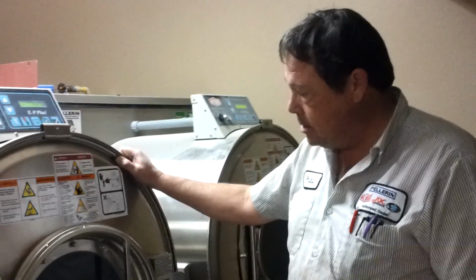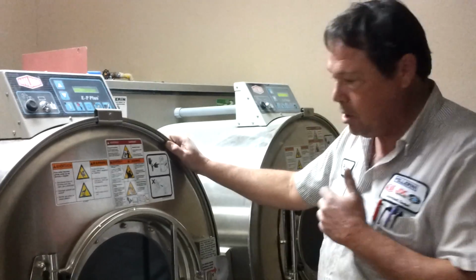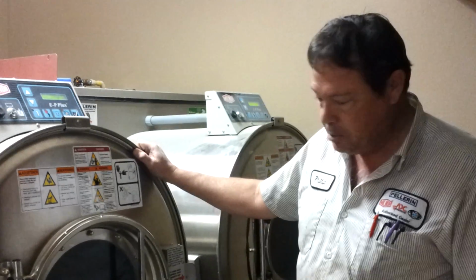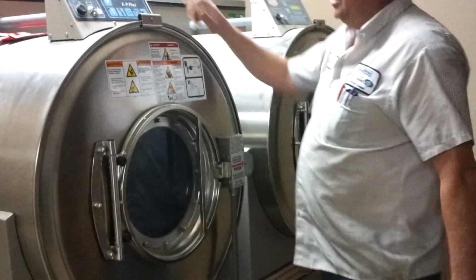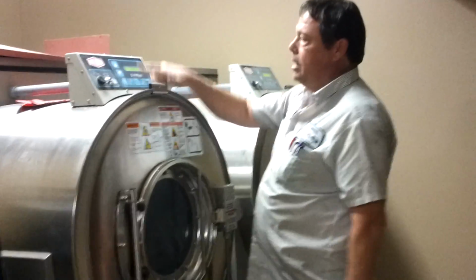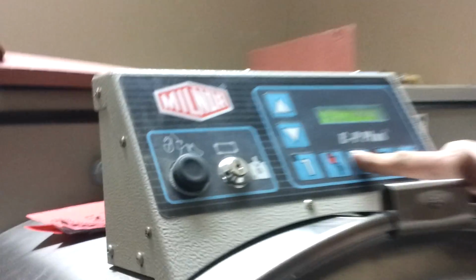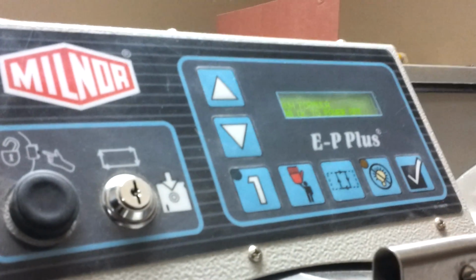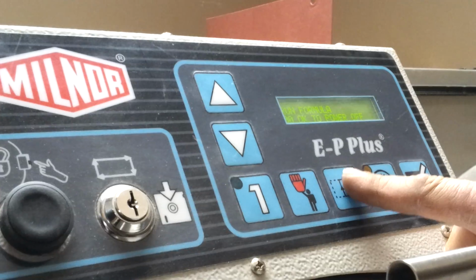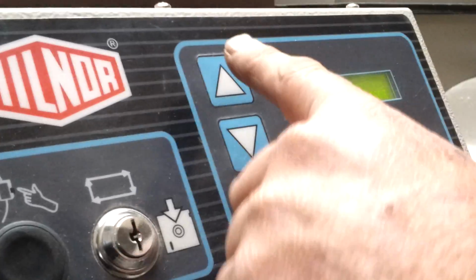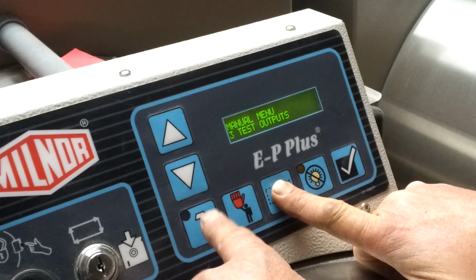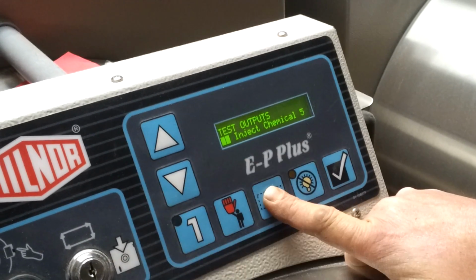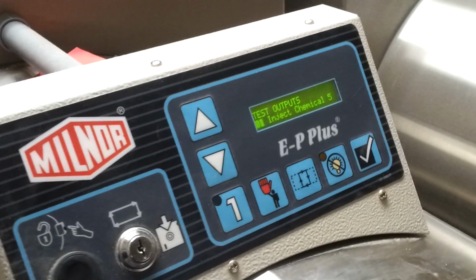So one of the biggest things that I need to show as far as maintenance and troubleshooting is, the door's got to be closed, but up here on your control panel you have these keys. And this key right here kind of has the square that goes around and around like this. To go into a manual menu, you want to push and hold this key and then come to this top key and go to outputs. Then once you get to outputs, while still holding this button, you press the 1 button. That puts you into a manual menu.